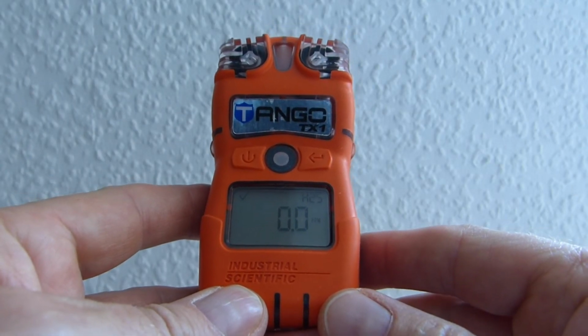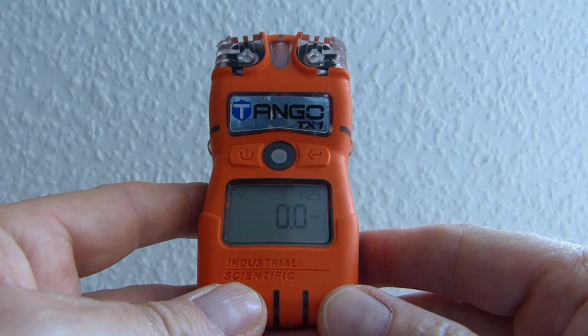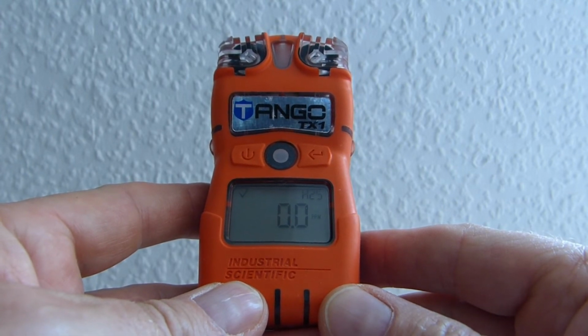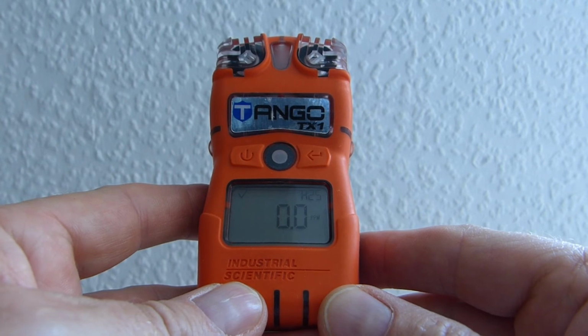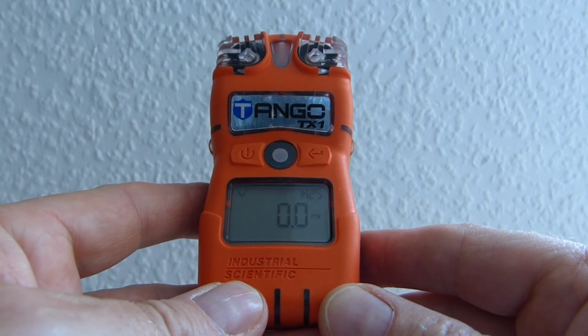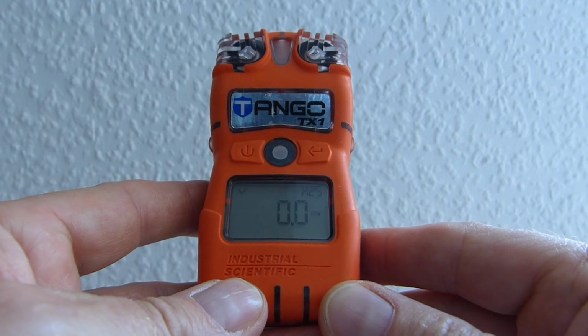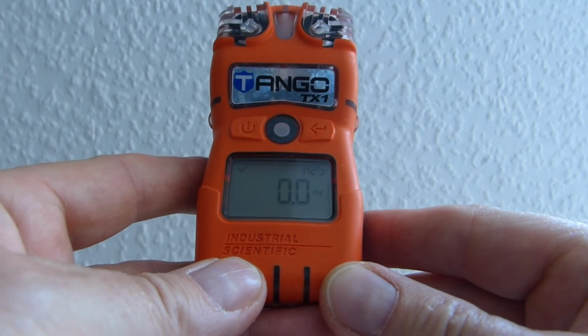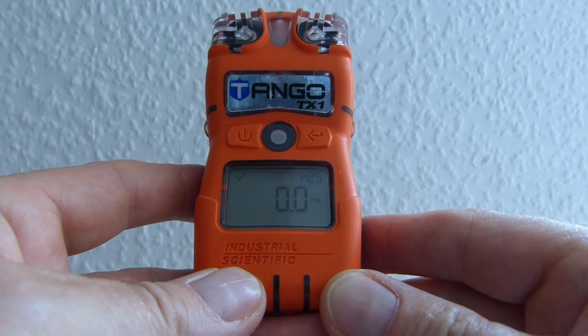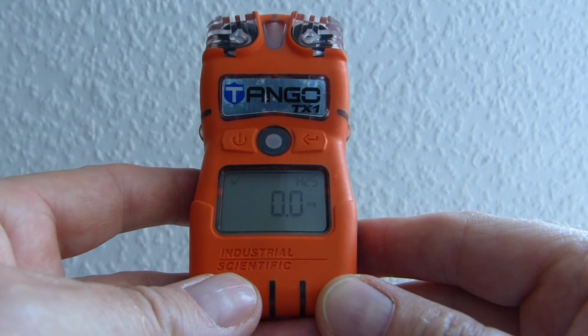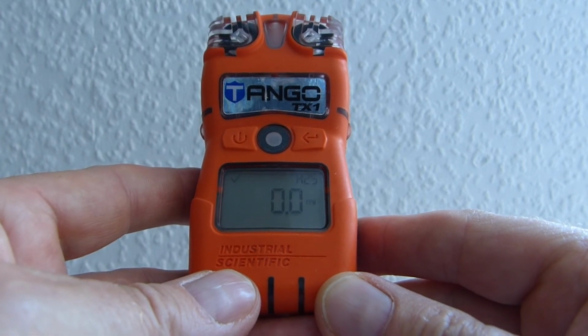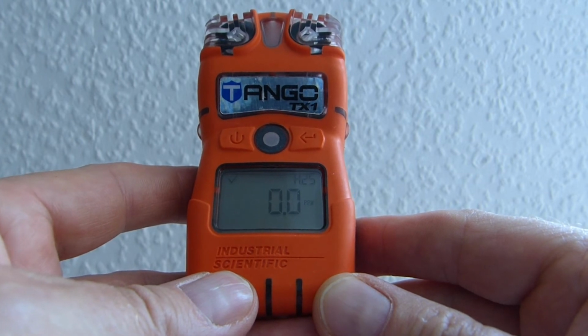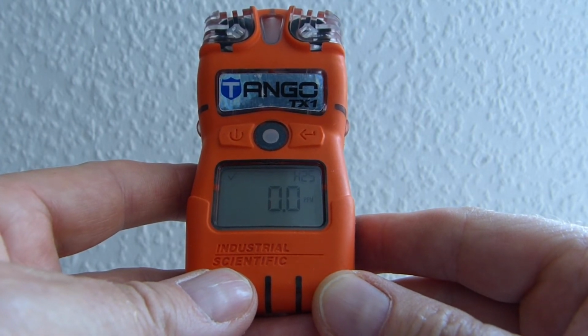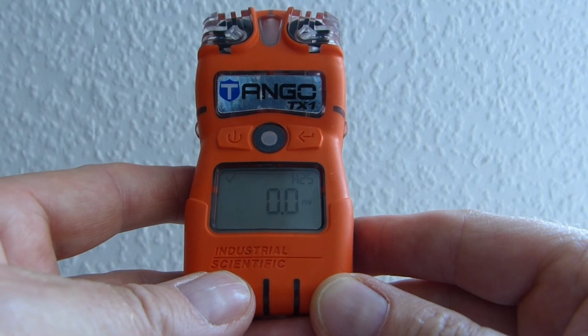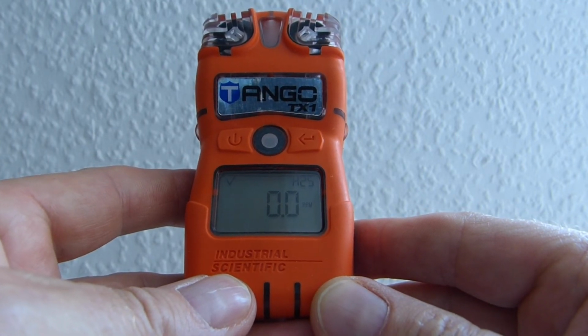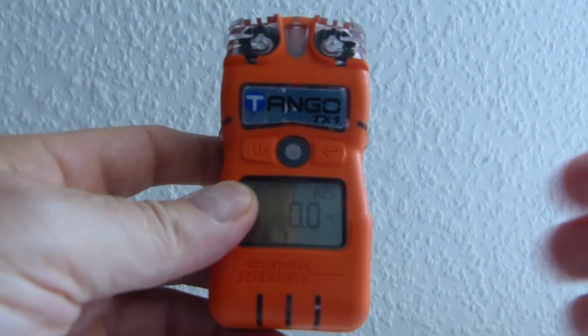Prior to the use of the Tango TX1 gas monitor, you have to make sure that the protective cover on the display is removed, and that a calibration using the automatic calibration station is performed. The factory test report that's in the box of the instrument assures that the instrument has been quality checked and calibrated at factory level. As the environmental factors in your regions are different, you definitely need to perform a calibration first before using it.